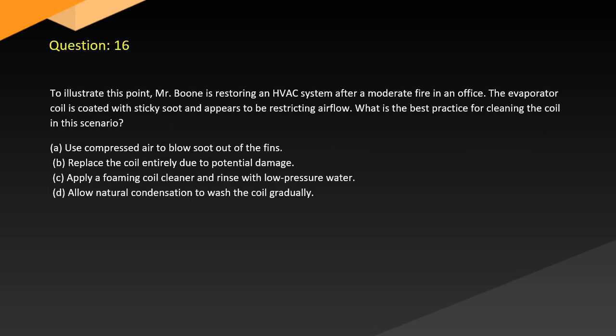Question 16. To illustrate this point, Mr. Boone is restoring an HVAC system after a moderate fire in an office. The evaporator coil is coated with sticky soot and appears to be restricting airflow. What is the best practice for cleaning the coil in this scenario? A. Use compressed air to blow soot out of the fins. B. Replace the coil entirely due to potential damage. C. Apply a foaming coil cleaner and rinse with low-pressure water. D. Allow natural condensation to wash the coil gradually.